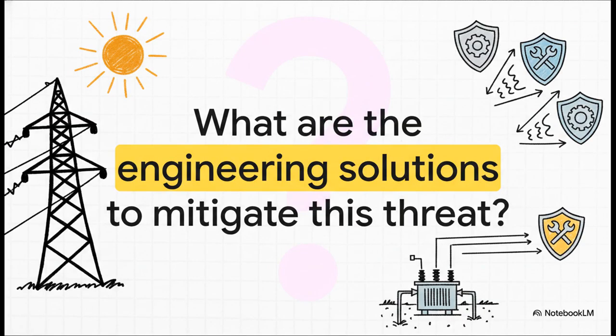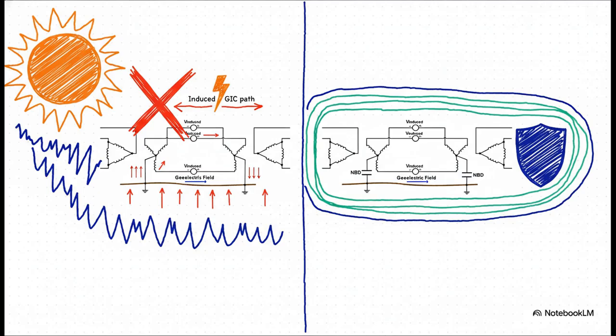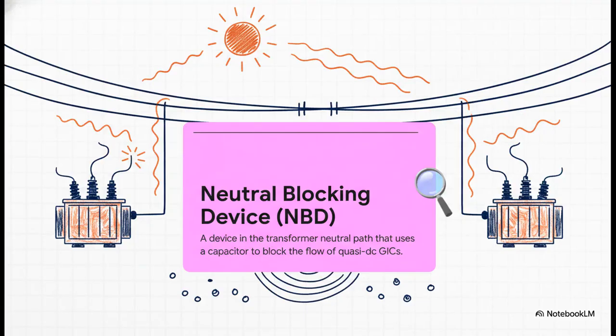Okay, so that's the problem. What's the engineering solution to all of this? Well, the most direct approach is pretty clever: just block the GIC's path into the transformer neutral. We do this using a neutral blocking device, which basically acts as an open circuit to the GIC.